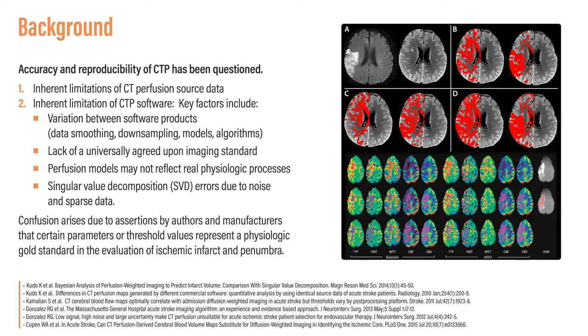In the last several years, the accuracy and reproducibility of CT perfusion has been questioned, due to several factors. The first is inherent limitations of the CT perfusion source data itself — noisy data in equals inaccurate results out. However, there are also inherent limitations in the CTP software itself: variation between software products, lack of a universally agreed upon imaging standard, perfusion models that may not reflect true physiologic processes, and singular value decomposition errors due to noise. Additionally, confusion arises from assertions by authors and manufacturers that certain parameters or threshold values represent a physiologic gold standard in the evaluation of ischemic infarct and penumbra. As you will see in this presentation, this is not necessarily true.